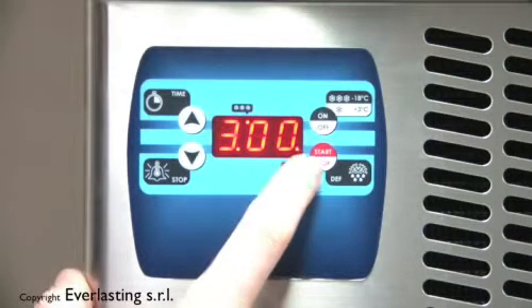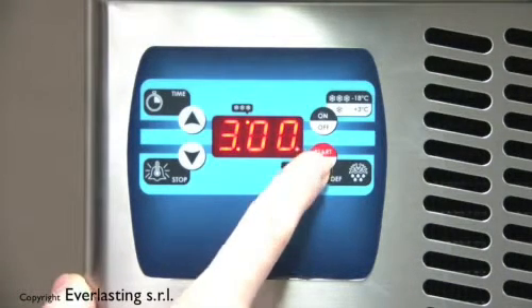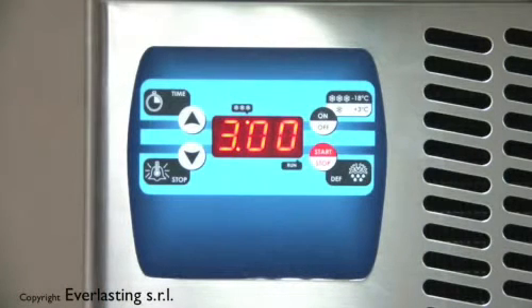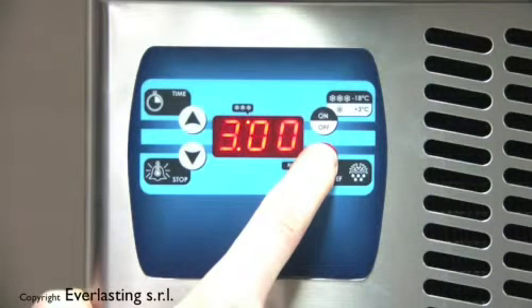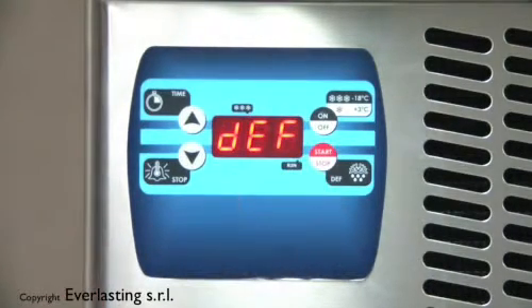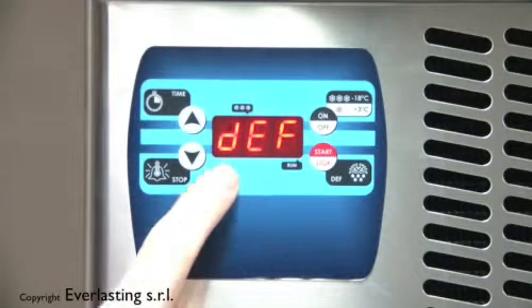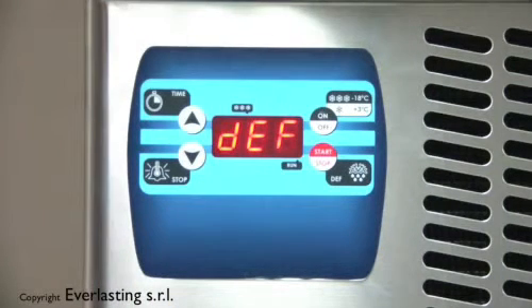At the end of the day, the machine performs the defrosting cycle. In this model it is done manually. To start defrosting, press the Start/Stop key for 5 seconds while the machine is in standby, off. The display will show DEF, which indicates defrosting. We advise doing this process with the door open, to speed up defrosting. The defrosting process will take about 20 minutes. After that, set the machine to standby.